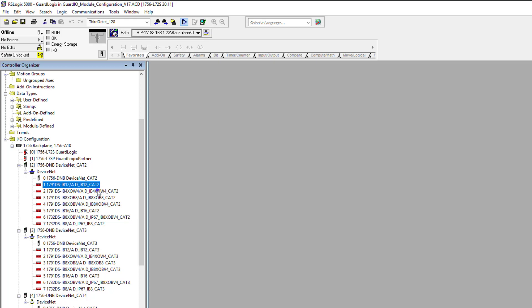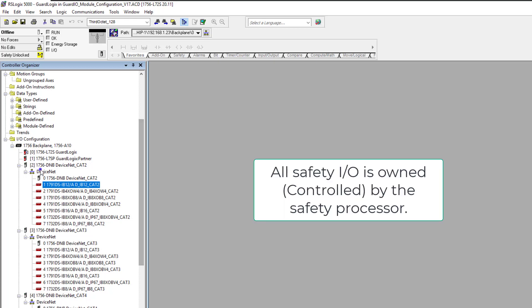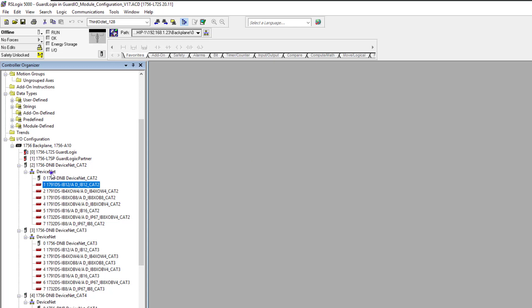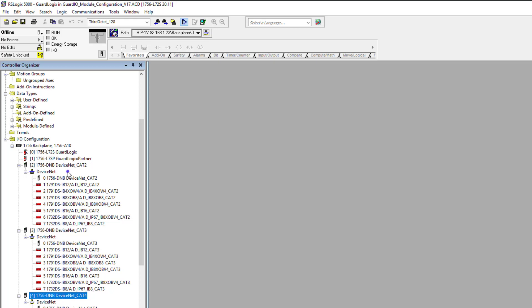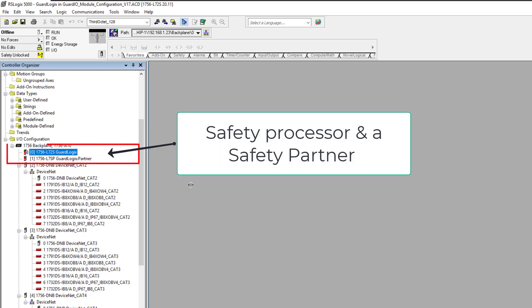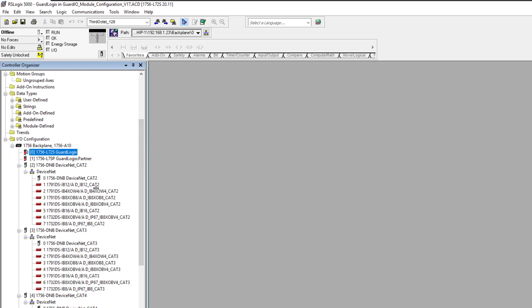However, the safety protocol is that the device is owned by the safety processor. All the devices inside each one of these settings, each one of these cards, is going to be owned by the safety processor. The safety processor has two actual processors - a processor and a backup processor, a spare processor, because it scans it twice. It does a double check of making sure the safety is doing what it's supposed to do logically. And it also checks things like IO.